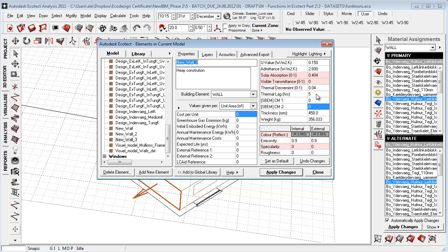It's actually only updating the u-value and the thermal decrement. It's not updating thermal lag and admittance as it says. Some of these parameters are quite well known but are working a bit differently inside Ecotect. The u-value is quite logical. Most people know this.